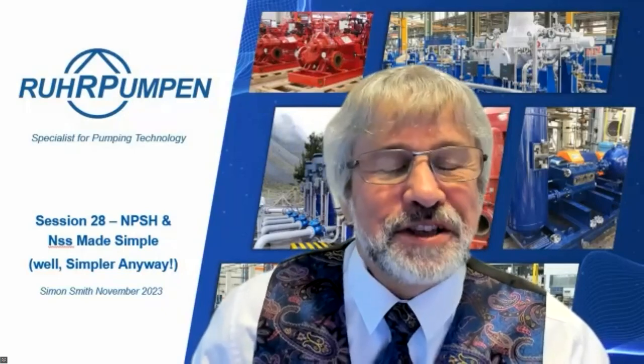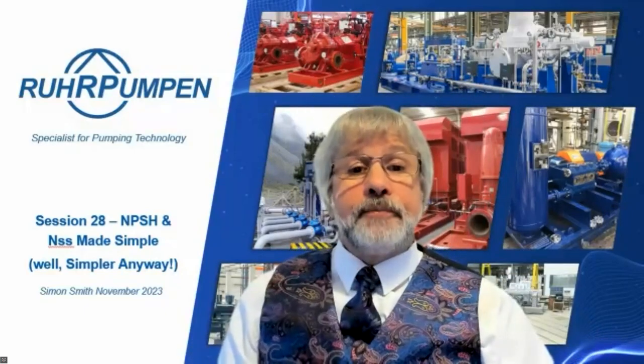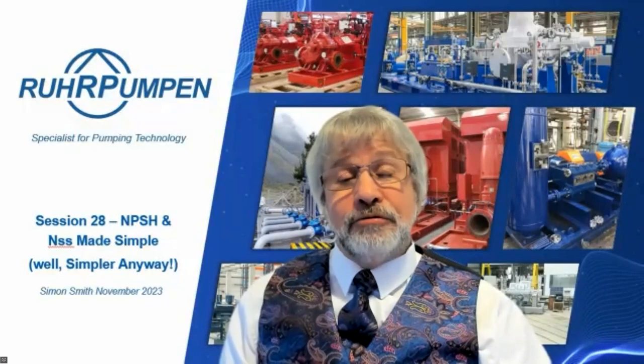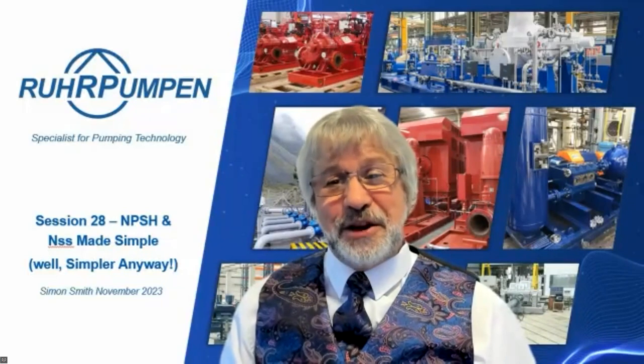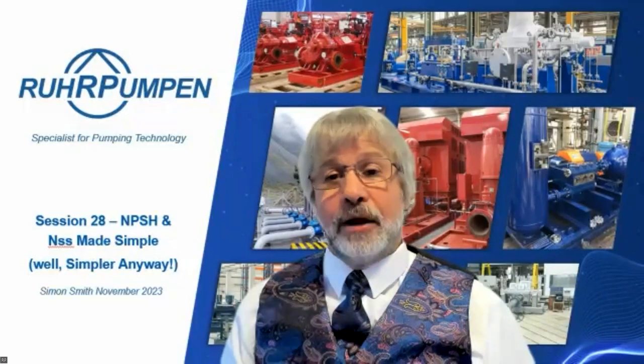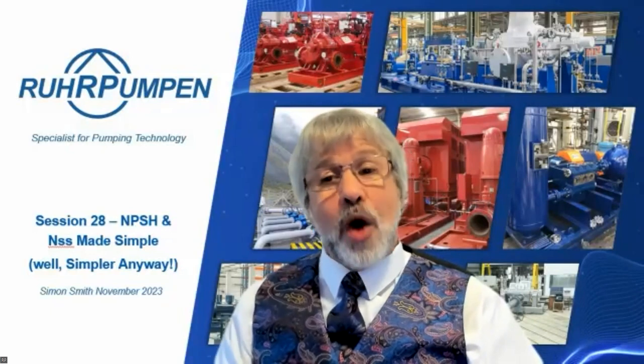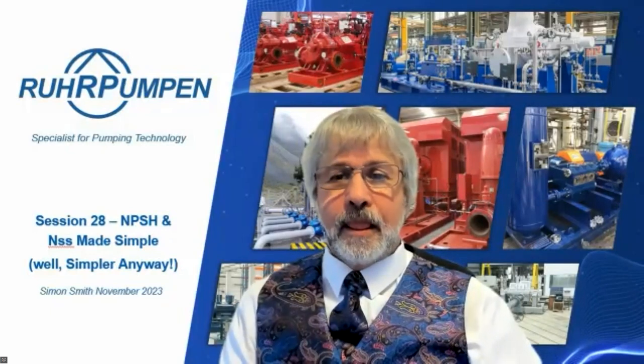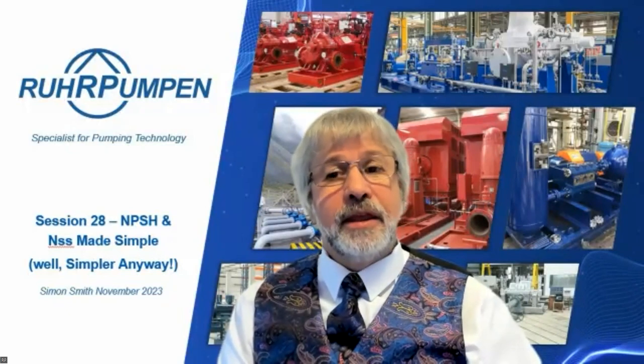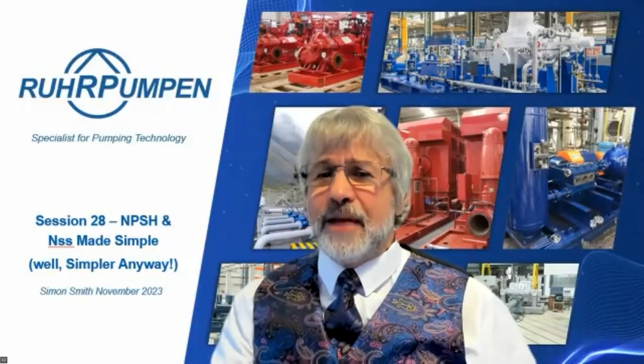Narasimhan Krishnaswamy asks: how does operating a pump on a variable speed drive affect the NPSHr? It does affect it. If you speed up a pump the NPSH required will go up; if you slow the pump down it will reduce. You can't simply use the affinity laws - speak to the pump vendor for that particular pump. Generally, if you slow a pump down the NPSH moves by approximately the square of the speed difference, but when you speed up, the NPSH will be higher than the square law would predict. Use the square law as a first guess but expect the actual NPSH to be higher.